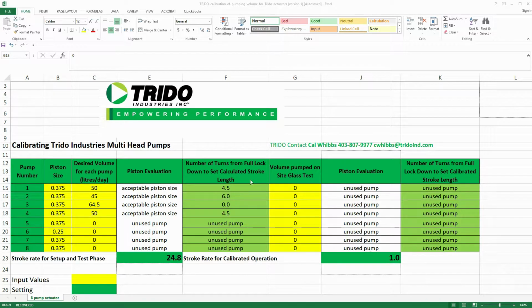Back at the computer, put the recorded sight glass values for each pump in column G. Ensure the remaining values in this column are all 0. Column J will confirm if the pump is a correct size or if it needs to be changed. Column K will give us the calibrated stroke length required for each pump. Compare the values in column K to the values in column F to see if there is any adjustments required.